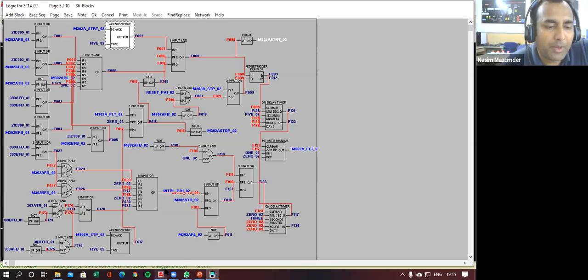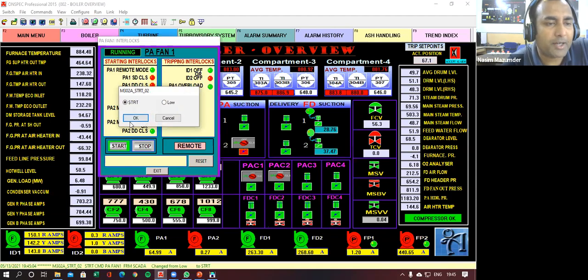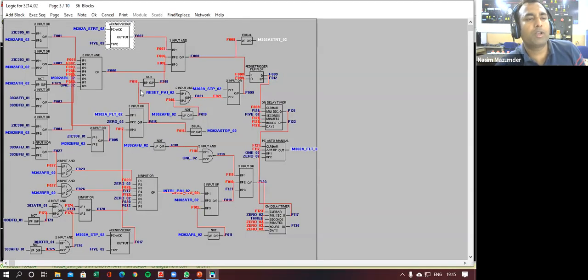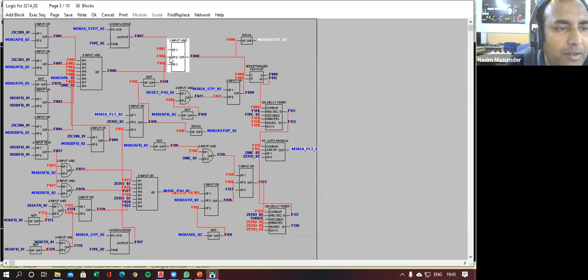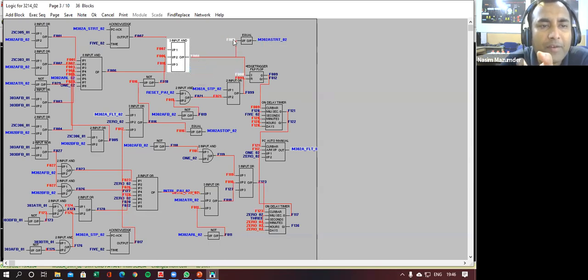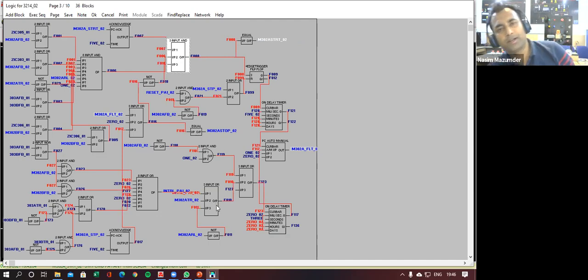The moment I give a command here, start, after that this block will hold the signal for 5 seconds. In between these 5 seconds, once this is high, there is an AND gate. So in between these 5 seconds, if both these pins, input 2 and input 3, go high, then this F008 will become high. And if F008 is high, there is an equal block, so this will become high and my motor will start.